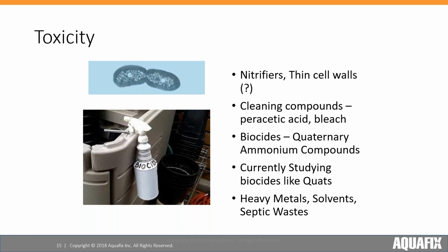When they're sprayed on the surface, ultimately they end up getting washed down the floor drain and eventually into the wastewater plant. For systems where you have a lot of dilution with other processes and other types of influent, these biocides get diluted out and they're probably not a problem. However, if there's a large dump or a processor that uses a lot of biocides makes up a large percentage of your influent, then this can quickly become a problem. These issues are generally compounded when it happens during the winter, where if you get a slug load of biocide or heavy rainfall event and a washout, the nitrifiers will be much slower to repopulate the plant in winter, and they can just end up taking too long to get your nitrification levels back up to where they need to be.